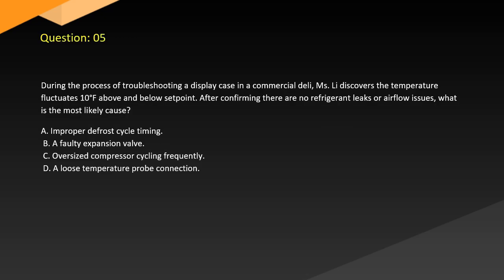Question 5. During the process of troubleshooting a display case in a commercial deli, a technician discovers the temperature fluctuates 10 degrees above and below set point. After confirming there are no refrigerant leaks or airflow issues, what is the most likely cause? A. Improper defrost cycle timing. B. Faulty expansion valve. C. Oversized compressor cycling frequently. D. Loose temperature probe connection.